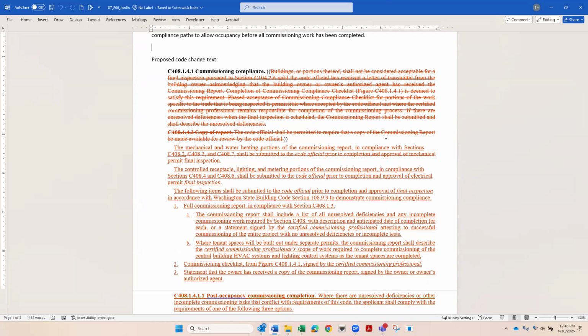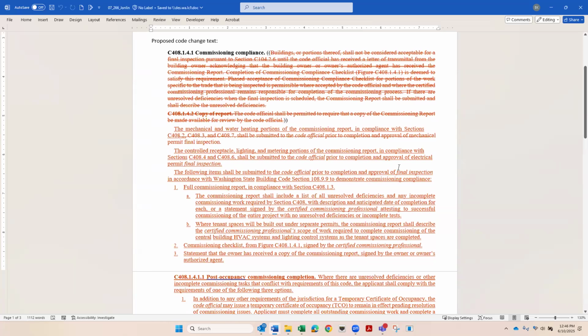If you look past that original language, which I found very confusing as written, what we've got—straight from Seattle's experience and worked out with our tag—is that the mechanical and water heating parts of the commissioning report have to be submitted before the mechanical permit final inspection is wrapped up. Likewise, the lighting, controlled receptacles, and metering parts have to be submitted before the electrical permit final inspection is wrapped up.